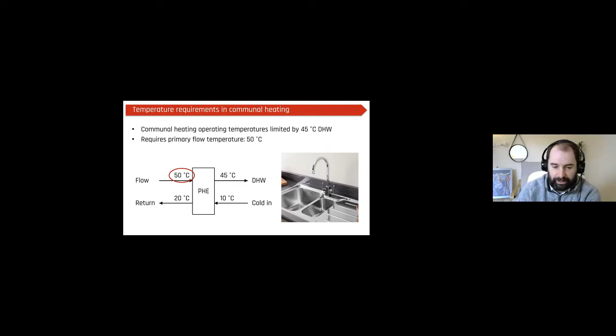On the image at the bottom, that means on your plate heat exchanger you need to provide heat on the primary side of 50 degrees to ensure you can get 45 degrees out for the resident to use. Another way of presenting that: anything above 50 degrees primary flow temperature is what I'd consider 4th generation, and anything below a primary flow temperature of 50 degrees I'd consider 5th generation.